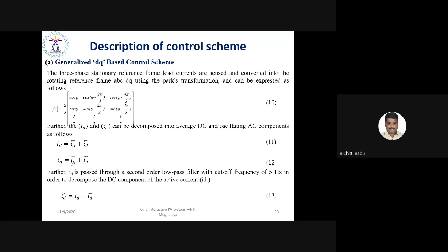So, the description of the control strategy: the strategy imposed on the controller of the inverter. The input parameter to the inverter is basically a DC parameter, the DC link voltage, and the outputs are the output voltage and current, the grid voltage and grid current. You have a transformation from ABC to DQ, so that the DQ components are orthogonal in nature. The D component is basically the active current component that governs active power control, and IQ is the reactive or quadrature component that governs the reactive power injection, right?